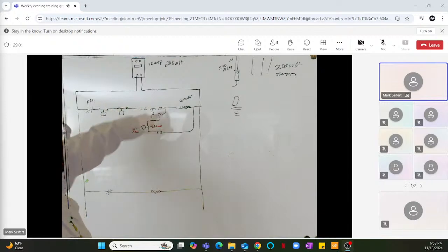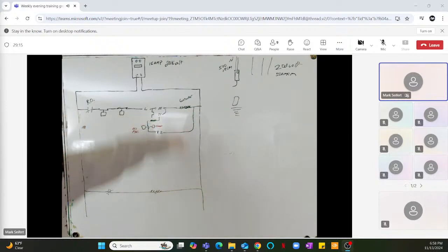If it keeps getting power for 30 seconds, it's going to be enough heat to take the temperature and push it open like a klixon. It's going to push it open, killing power to the compressor. That's what I'm going to say.